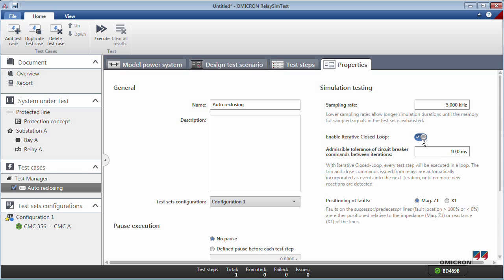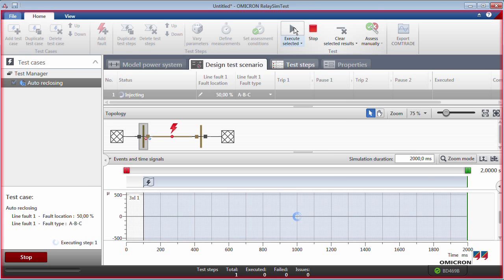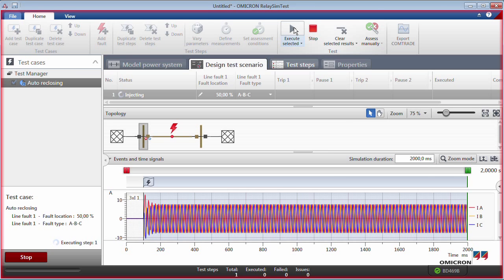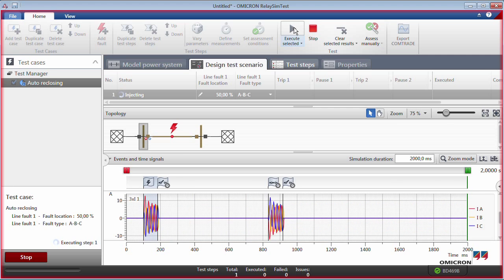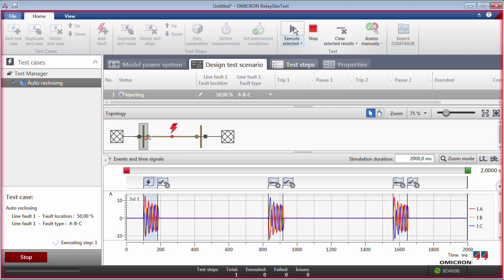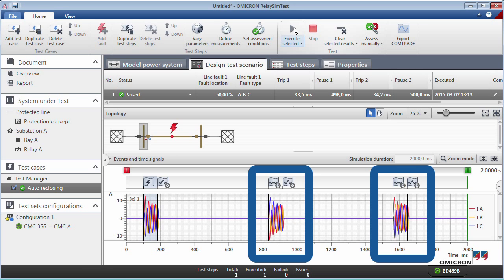After enabling Iterative Closed Loop, RelaySimtest automatically records the relay reactions and creates the simulation. As expected, the relay has locked out after two unsuccessful reclosing attempts.